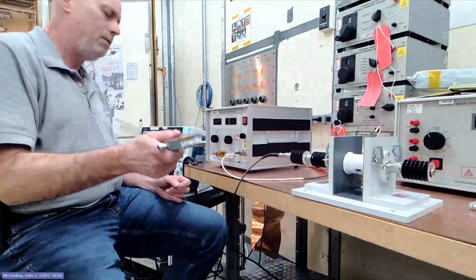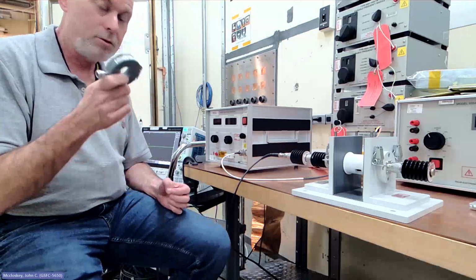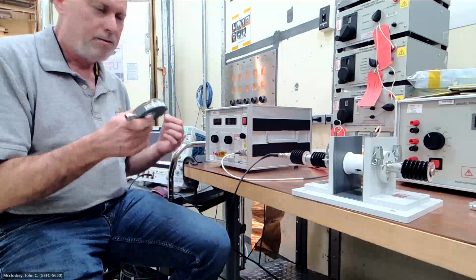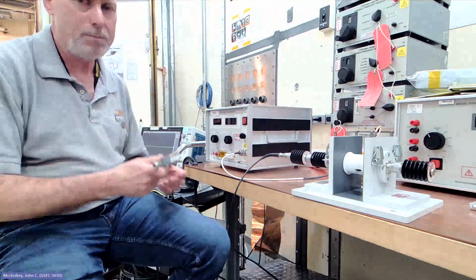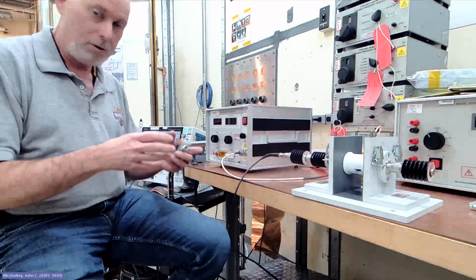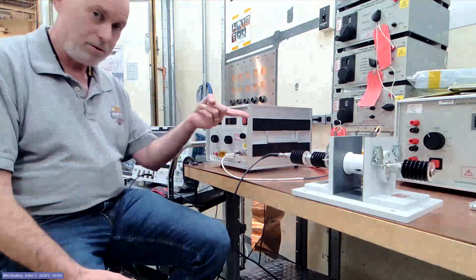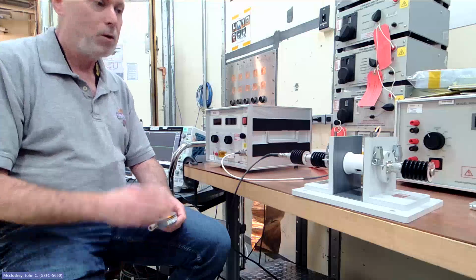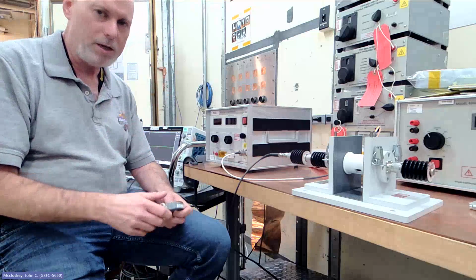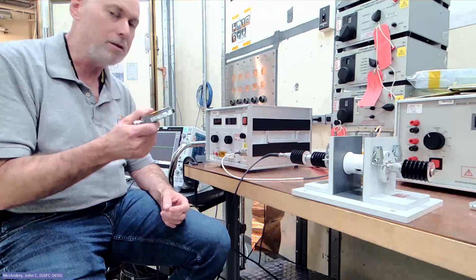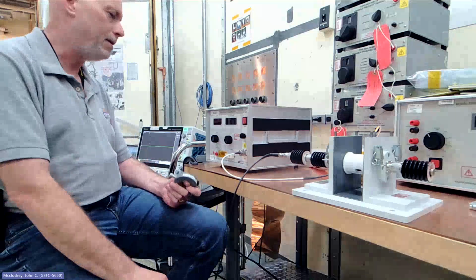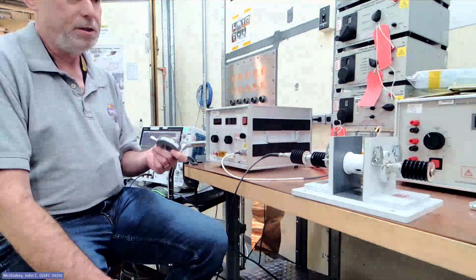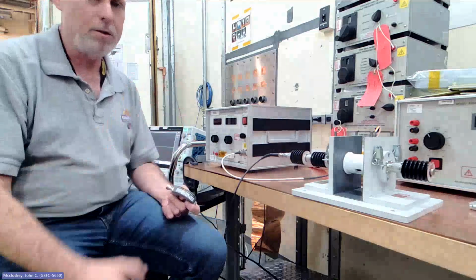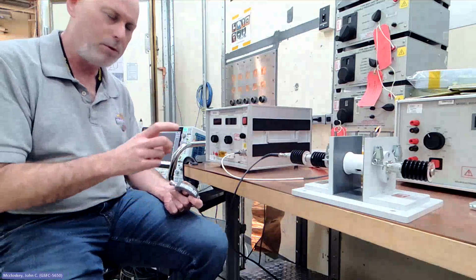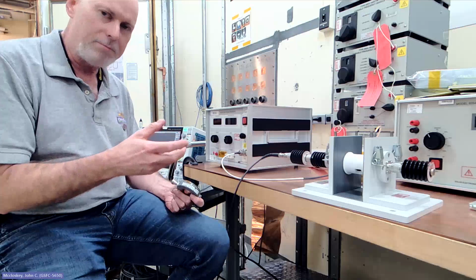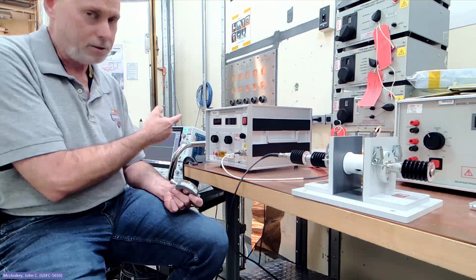This F65 current probe works up to a gigahertz, and it has a flat transfer impedance of 1 ohm from about, I believe, a couple of megahertz up to a gigahertz. So it's good for using. We can use this for time domain measurements at higher frequencies in the range of this waveform here. We're looking for those rise and fall times of about 1 to 2 nanoseconds, so we should be able to see that with reasonable fidelity. It's the best current probe that I have for looking at that. And the 1 ohm transfer impedance means that what we see in volts on the scope equals the current in amps. So if we're looking to see something that's about 5 amps, then we're going to see about 5 volts on the scope.